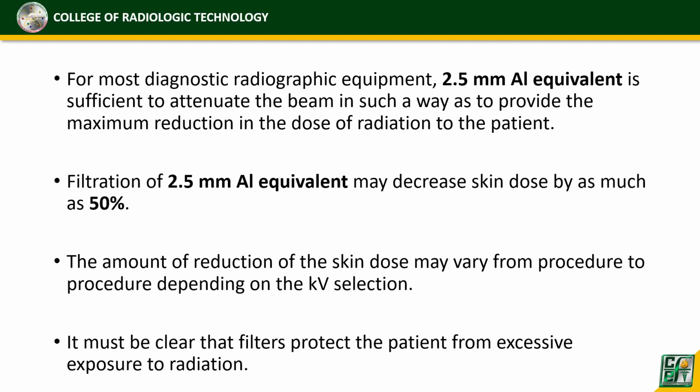So filtration of 2.5 millimeter aluminum equivalent may decrease skin dose by as much as 50%. So ganun ka significant yung filtration. Okay, particularly 2.5 millimeter equivalent filtration.